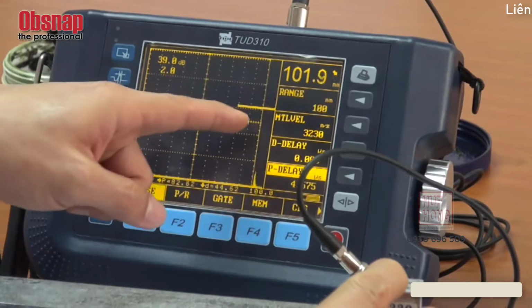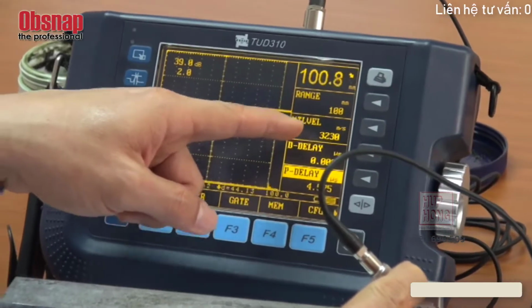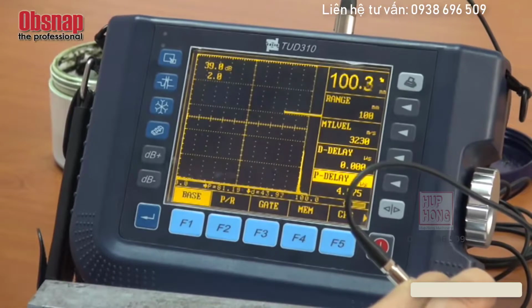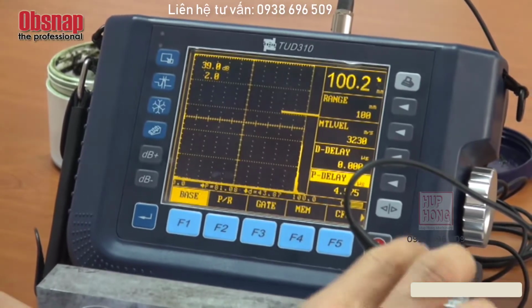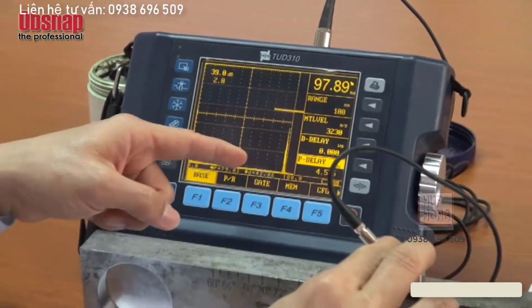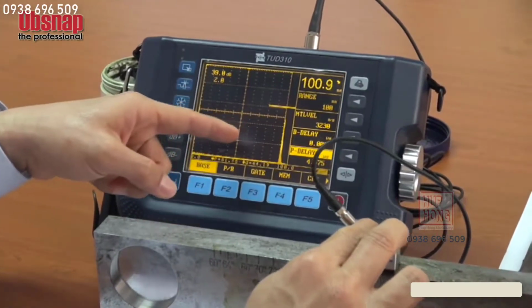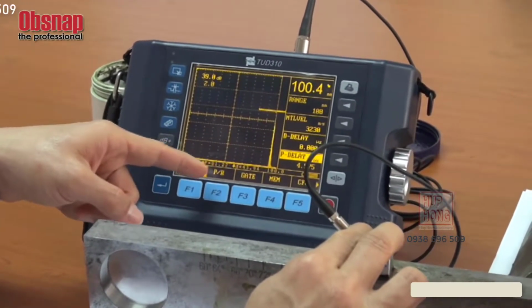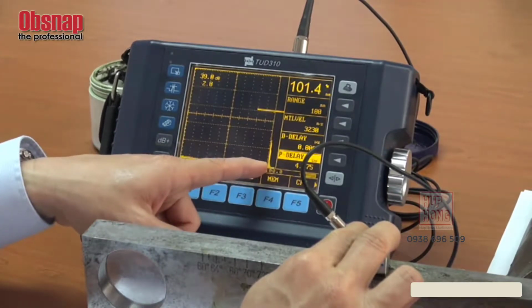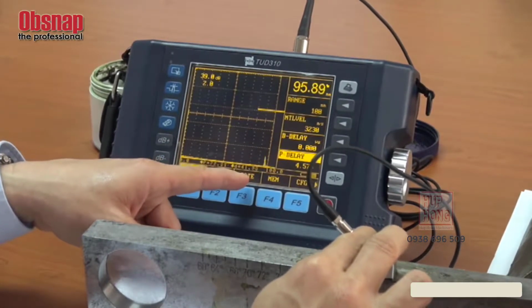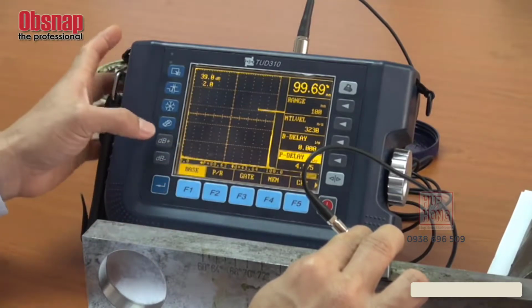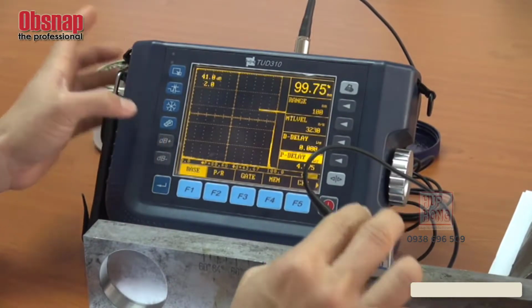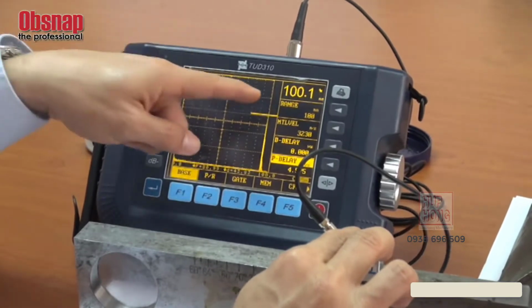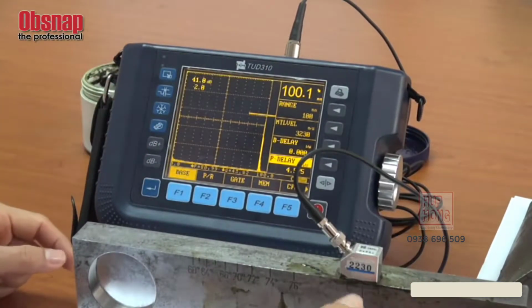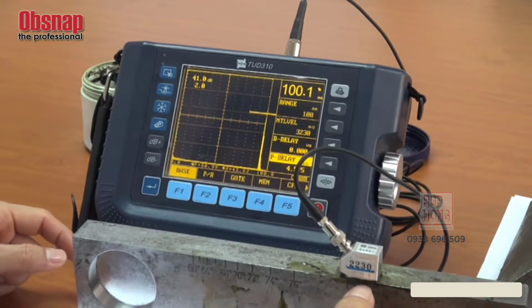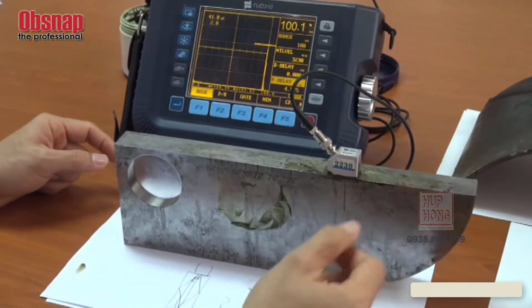So let's see. Yeah, this is the setting that is suitable for this probe. Why do I know? Because number one, the material velocity is 3230 for longitudinal wave for this angle. Right now you can see we are successfully getting a pulse. What is the reading? This range I have set to 100. I can increase the gain. Now what is the reading? 100. Why 100? Because this range is actually 100, from this slot.